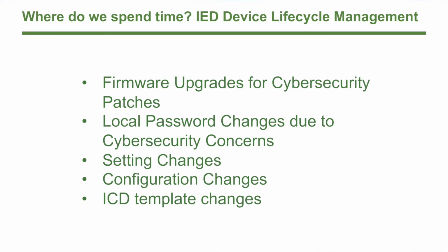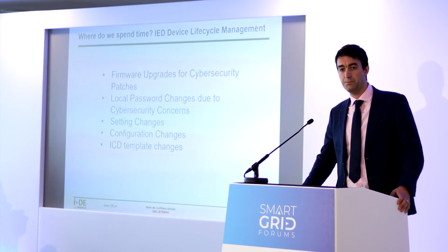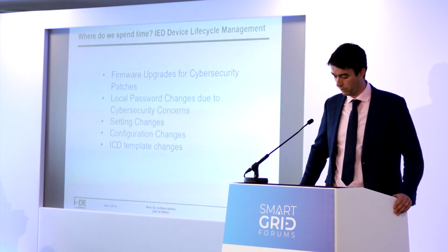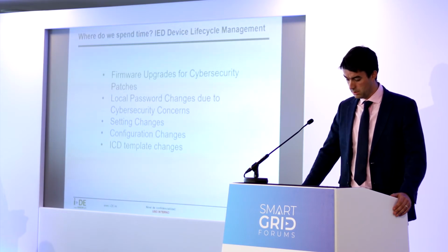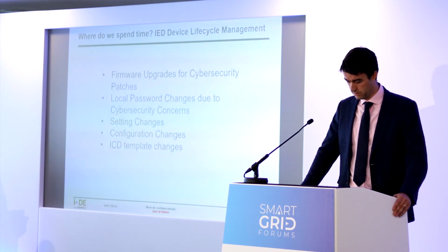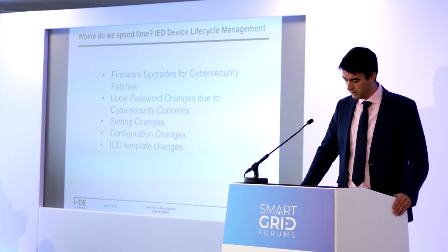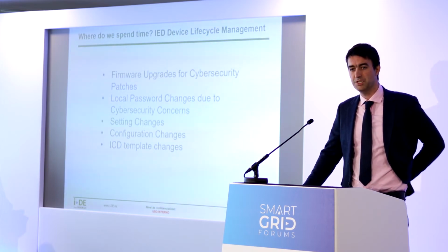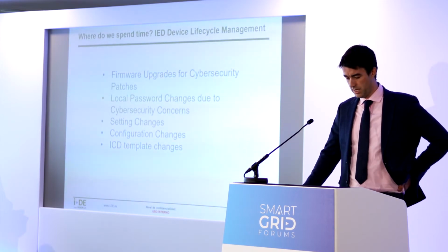in some ways, this time burden looks like it could even increase with 61850, with new cybersecurity burdens on the utility. For example, to upgrade the firmware to include a new security patch, or to change the local device passwords after a local access has been made. And then, from a configuration point of view, if we need to change a data set or another part of the ICD file, we would need to reproduce an SCD file and the reconfiguration of all the affected devices, and then go on site with all these new configurations and load them to all the relevant devices.